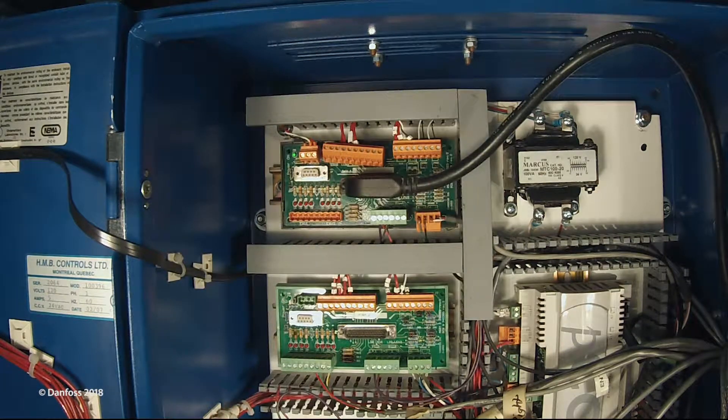When the compressor calibration is unusual or bearing faults are occurring, it is recommended to verify the PWM. Begin by disconnecting the compressor interlock and chiller controller connections from the IO board to prevent interference from external sources during testing.